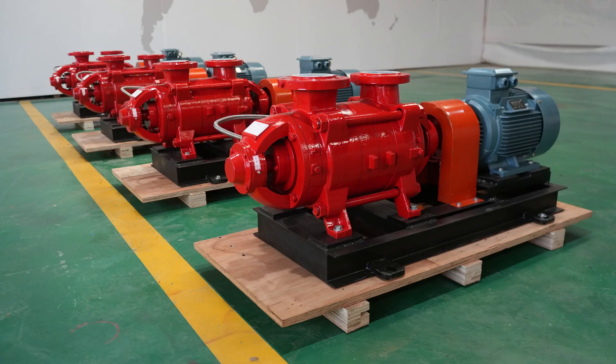Flow rate — how much water per minute, usually gallons per minute — needs to match the boiler's maximum steam demand. The pump has to supply enough water for peak demand. Like making sure your hose can actually water the whole garden. Too little flow and the boiler can't make enough steam. Beyond pressure and flow, physical space and layout matter too: room for a long horizontal pump, or does it have to be a tall vertical one? And thinking about maintenance access in the long run is also a big factor.